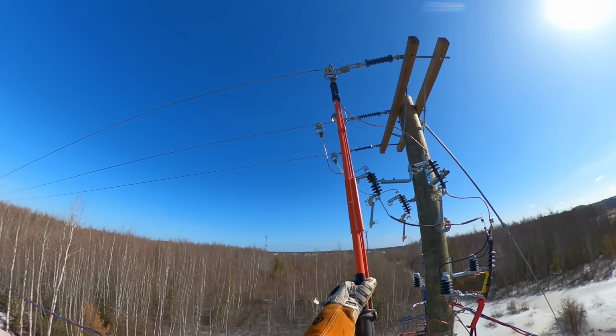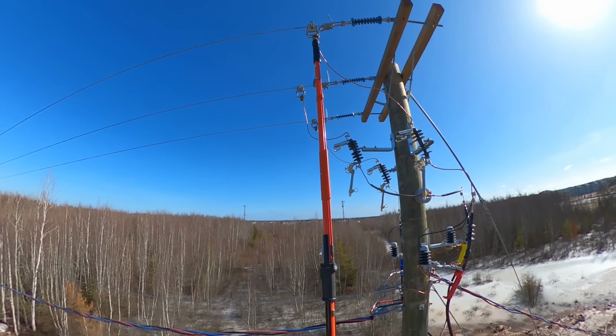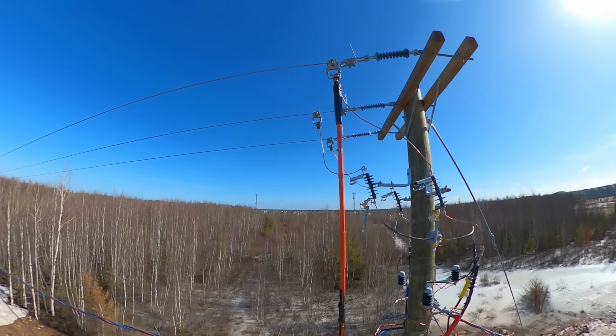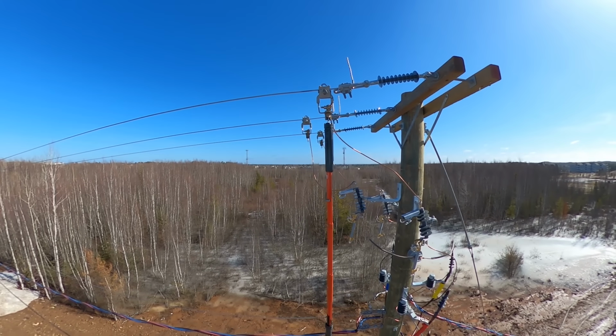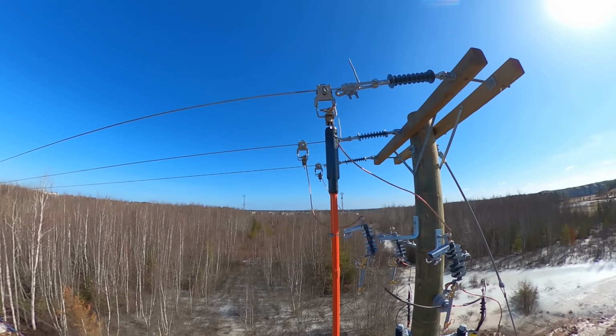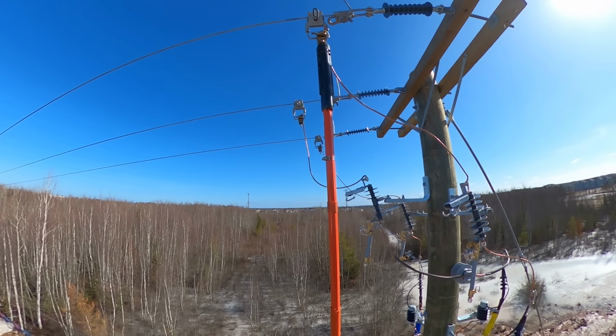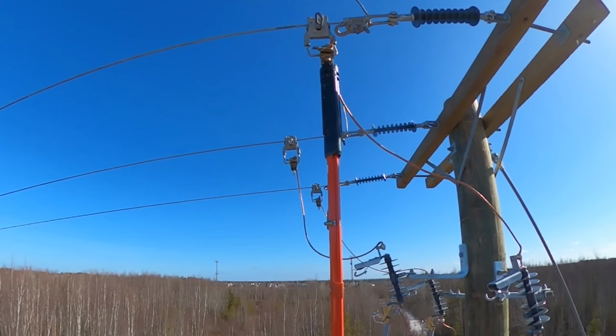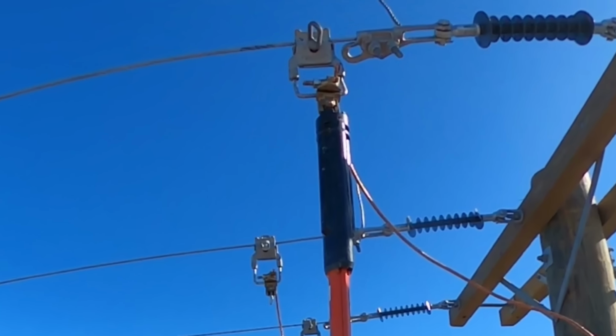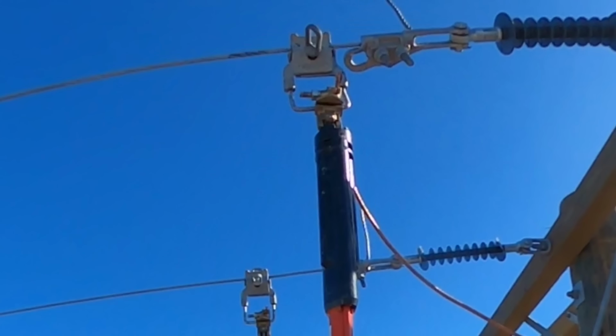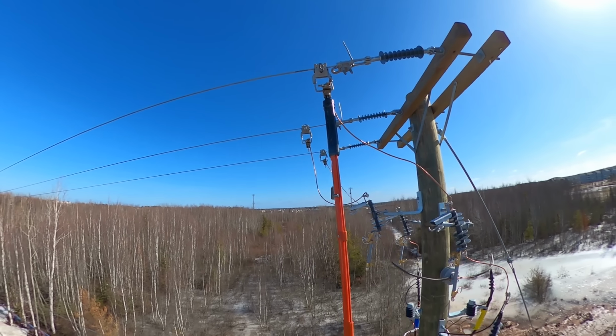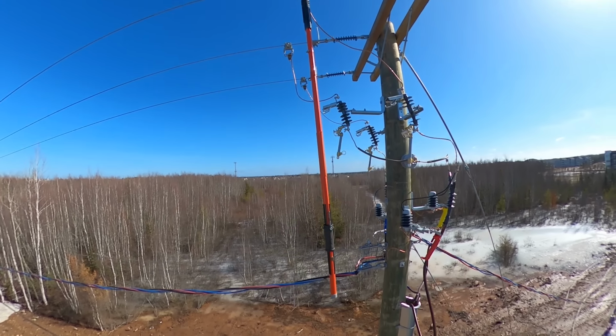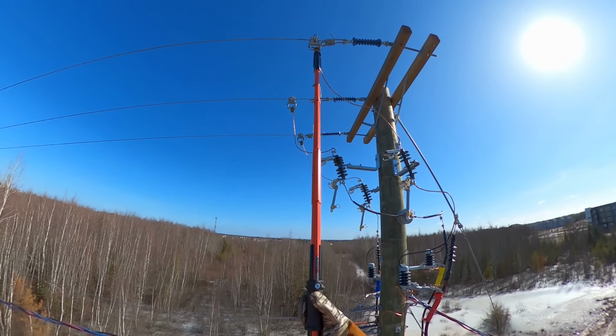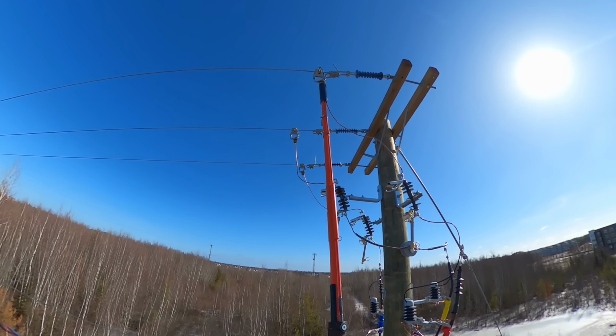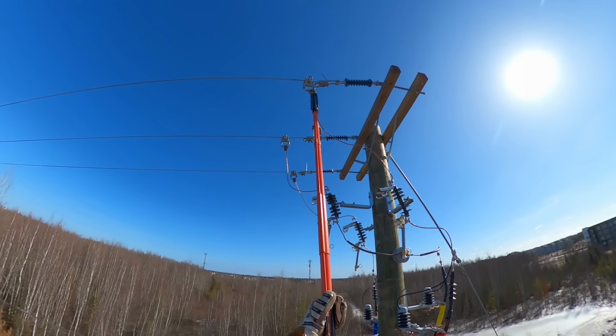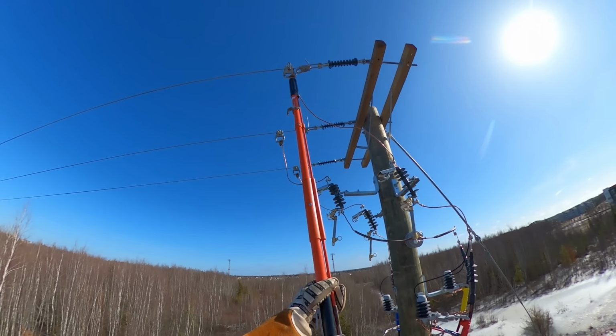Now if we were to leave that like that, I guarantee you within a year I'd be getting a call with some equipment up in the air. What happens is there's a little groove that the stirrup sits in, and as you're tightening to the right, it twists that tap clamp to the right, and you can see that it's lifted up on the left hand side a little bit. It's not fully seated in that stirrup or in the tap clamp. So whenever you're putting these on and it's all the way tight, just give it a little flick, roll it around a little bit, it'll slide into place, and you can see we got three-quarters if not a full turn out of that.